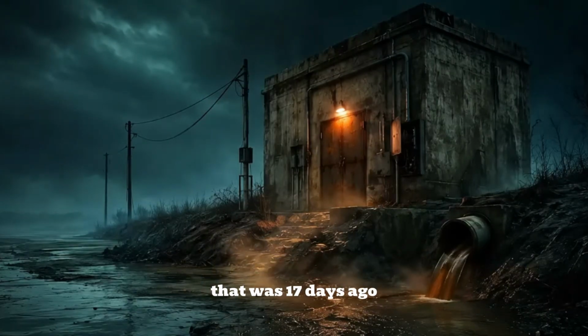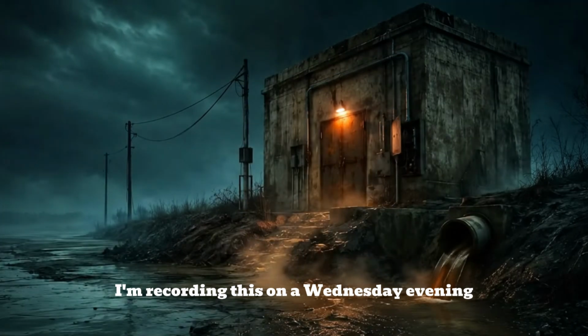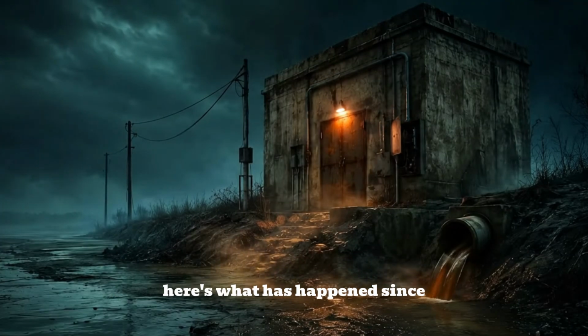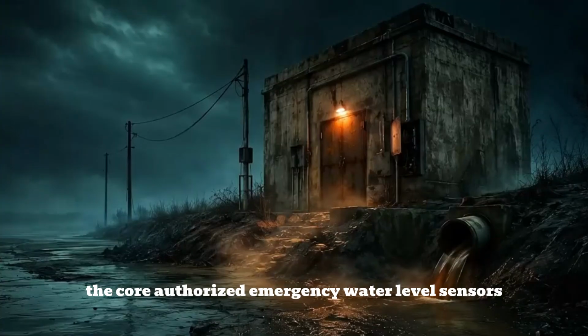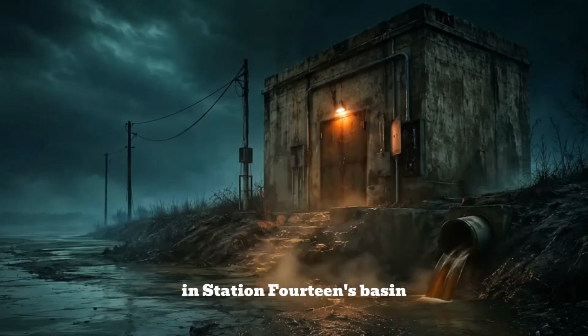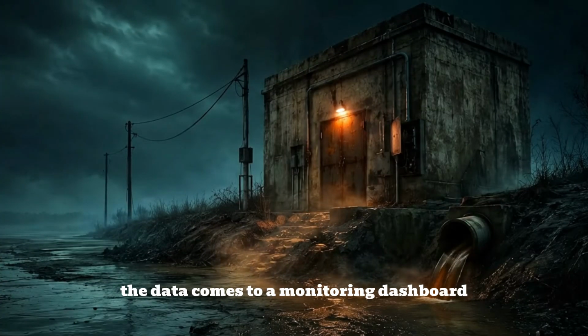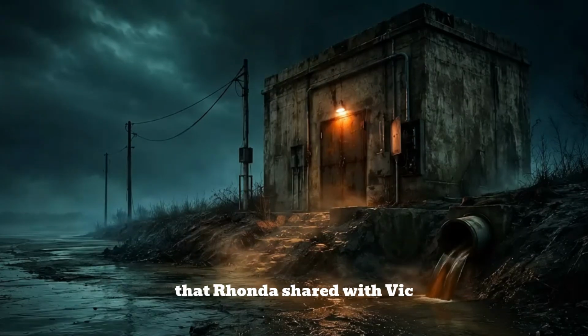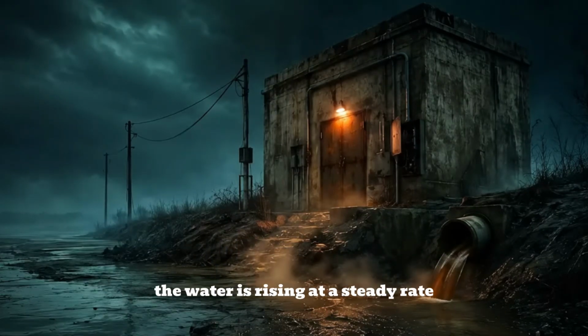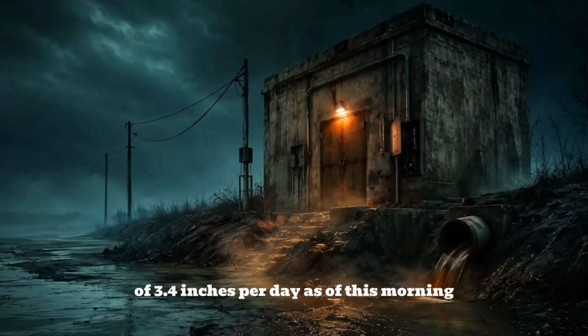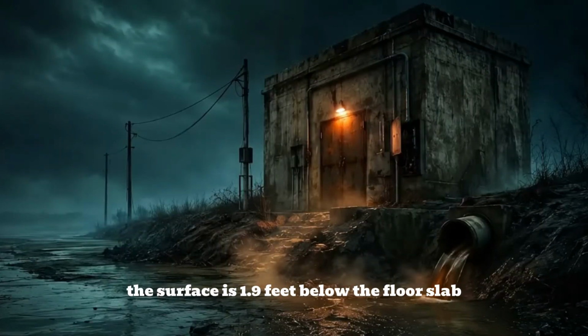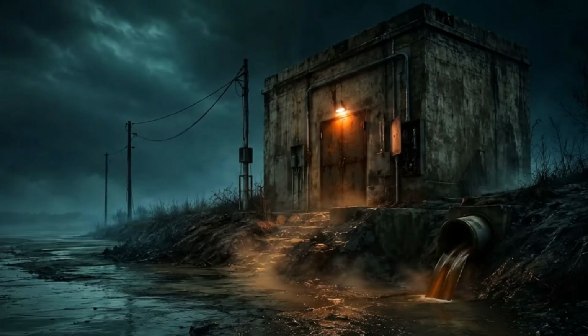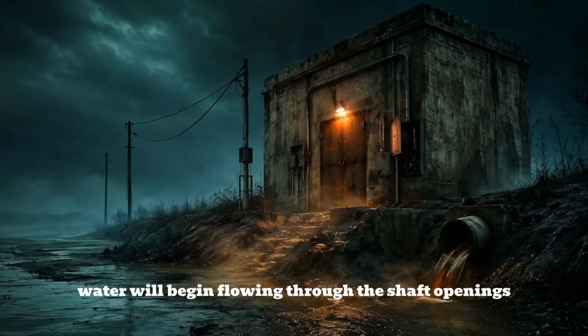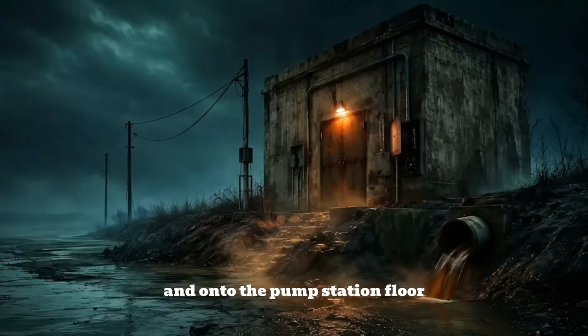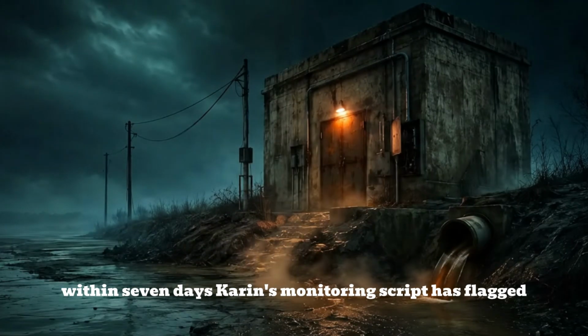That was 17 days ago. I'm recording this on a Wednesday evening. Here's what has happened since. The Corps authorized emergency water level sensors in Station 14's basin. The data comes to a monitoring dashboard that Rhonda shared with Vic, who shared it with me. The water is rising at a steady rate of 3.4 inches per day. As of this morning, the surface is 1.9 feet below the floor slab. At current rate, water will begin flowing through the shaft openings and onto the pump station floor within 7 days.